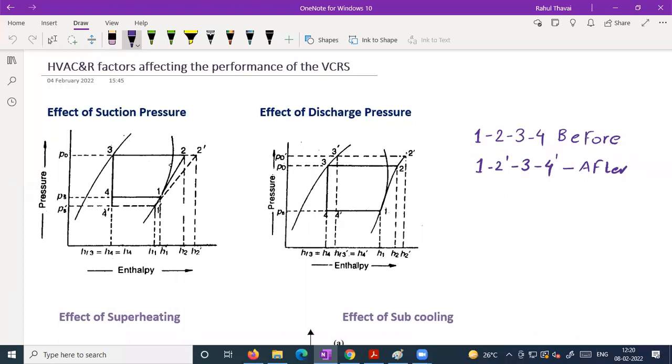But what happens is, the suction pressure actually decreases due to the frictional resistance to the flow of the refrigerant. Whatever refrigerant is flowing offers frictional resistance to the flow. As a result, ideally we want to get to point number 4. All of you see this point. We want it to be point number 4.